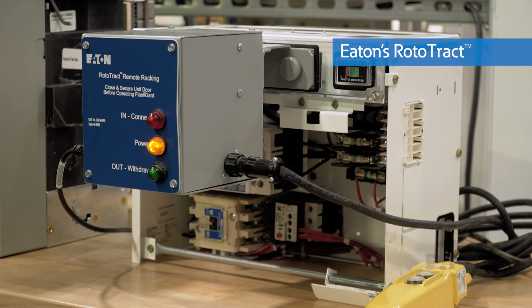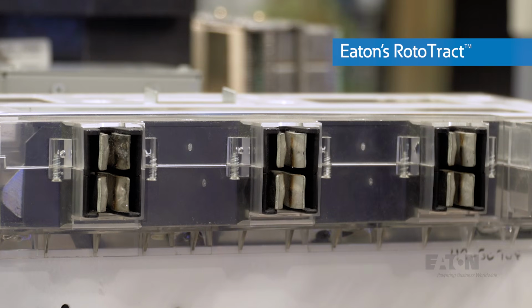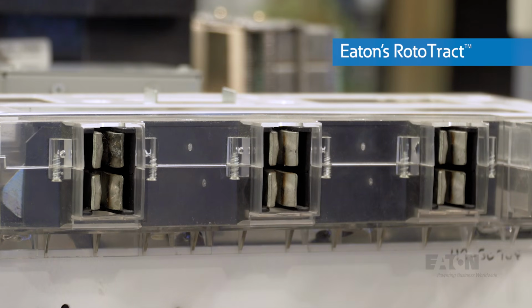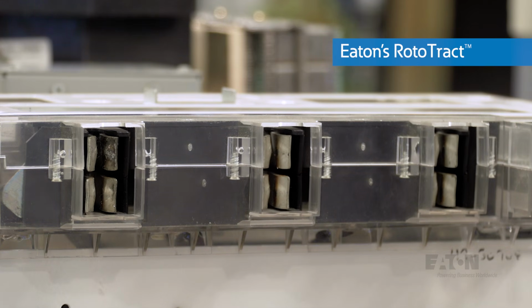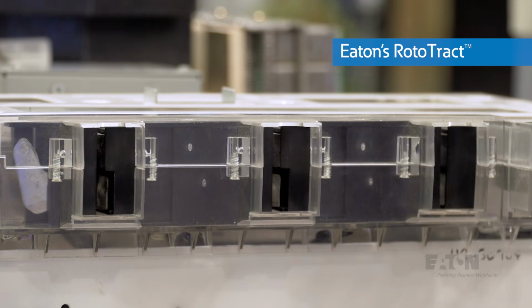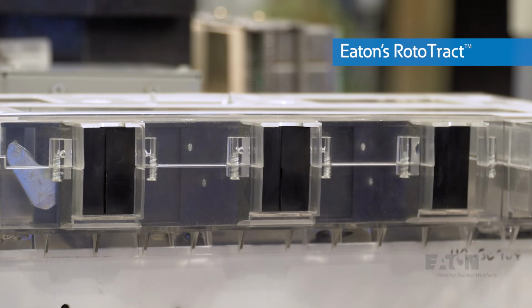For additional safety, Eaton's FlashGuard buckets are equipped with a retractable stab mechanism called RotoTract that withdraws the stab assembly off the energized bus bars and into the bucket. A spring-loaded shutter then automatically closes off access to the bus bars, which allows the electrical worker to connect and disconnect power to the bucket with the unit door closed, thereby minimizing exposure to arc flash.